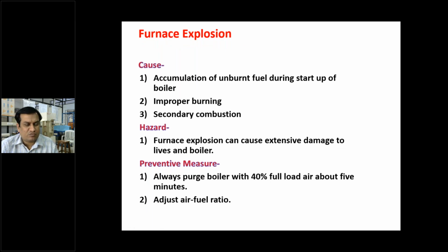So why may this explosion be possible in the furnace? The cause may be accumulation of unburned fuel during startup of the boiler. When the fuel is fed to the furnace, it is ideally expected that 100% of the fuel is going to burn with the help of excess oxygen.